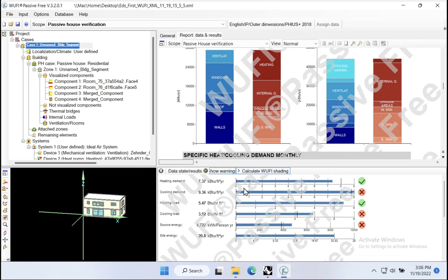Now we're not 100% done yet. We haven't fully modeled things like, if we have a kitchen extract hood, and there's some other bits that might still increase this number. But for now, based on what we know so far, it looks like what we've done to the envelope, R30 walls, R50 roof, 0.17 U-value windows, was good enough to get our heating energy demand and our peak heating load down below those PHIUS targets.